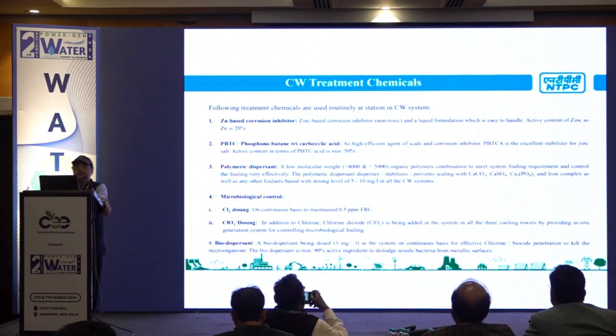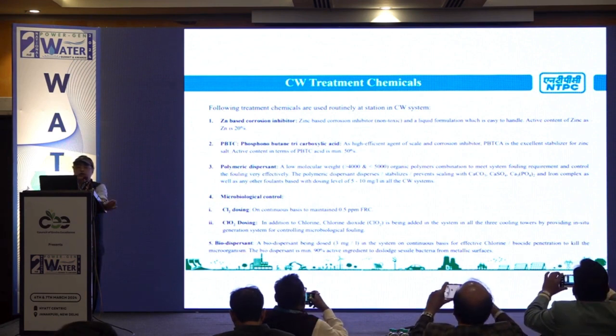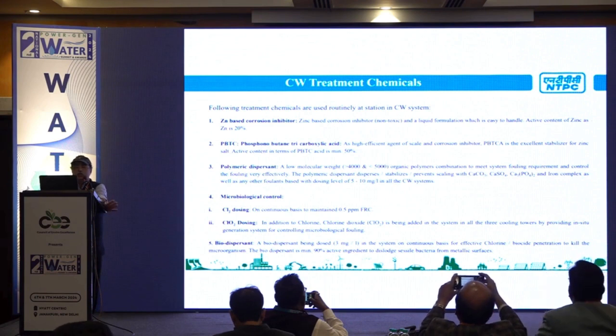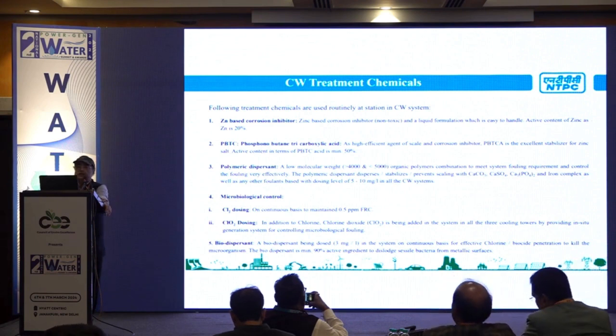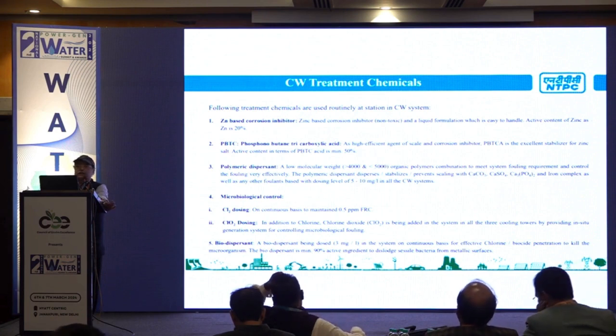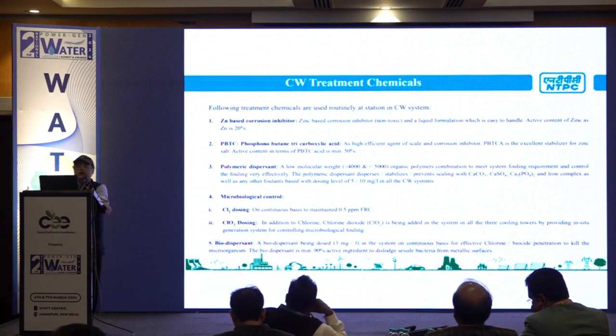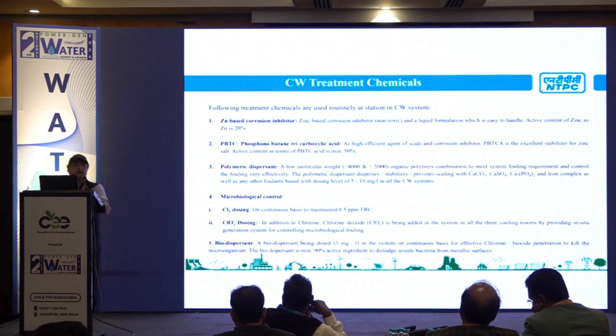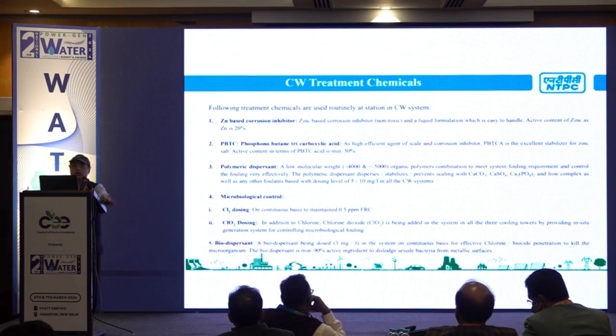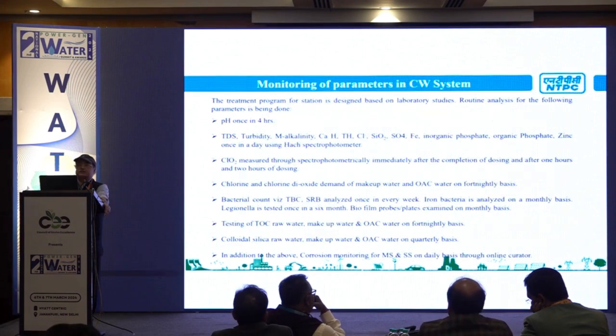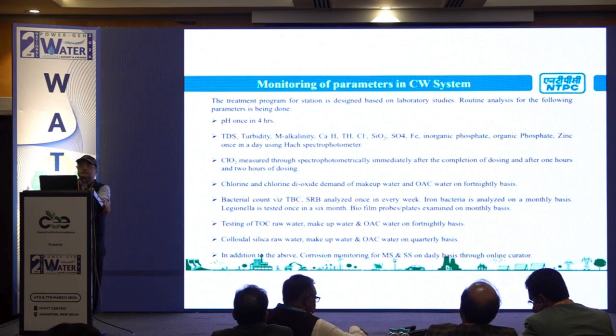We are using this treatment program: zinc, PBTC, polymer dispersant for microbial control and corrosion control, and biodispersant. Zinc we use at 0.5 to 1 ppm, PBTC 3 to 5 ppm, sometimes up to 10. Polymer dispersant 5 ppm, and biodispersant 3 ppm. Biodispersant is used at hold-up conditions, others on a blow-down basis.